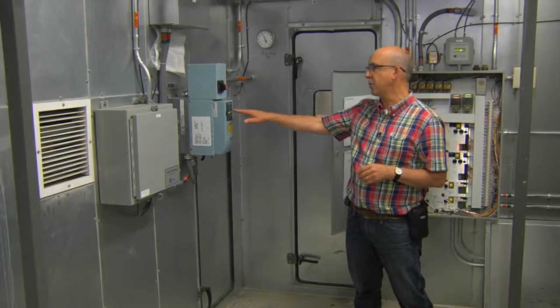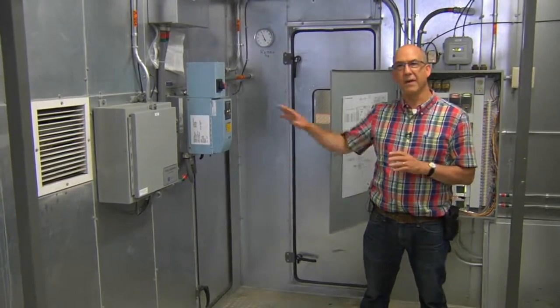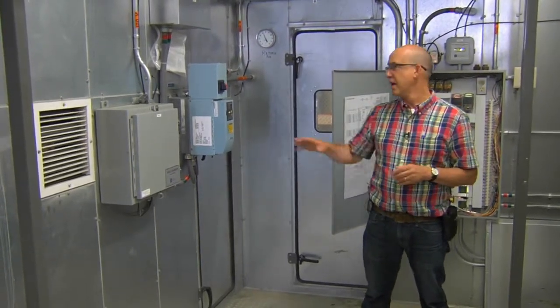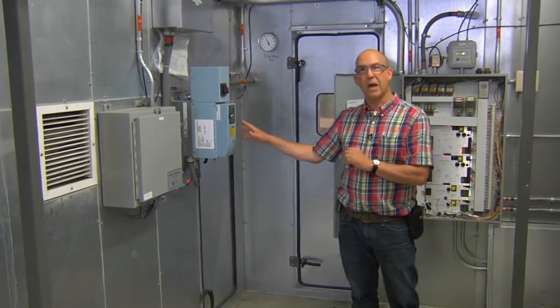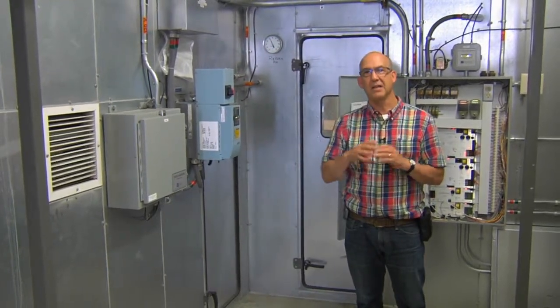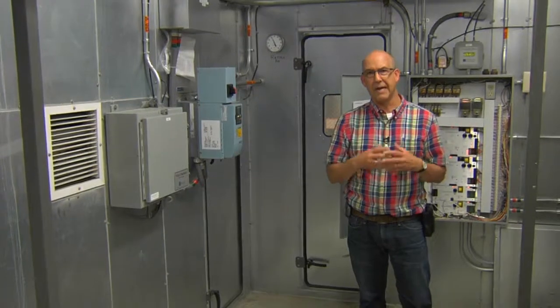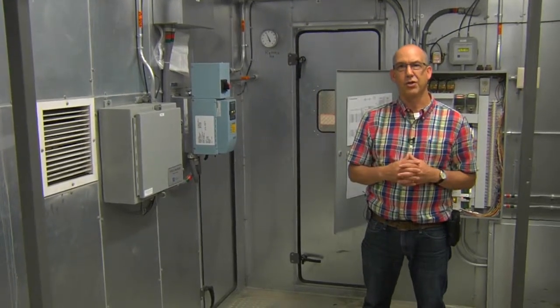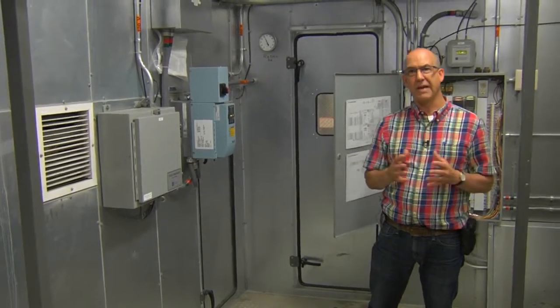We want to see stable output signal on VFDs, indicates good control. So in this case, the return fan's operating really well. The supply fan's behind us. The control loop, the PID loop might need to be looked at. There might be a sensor issue. It could be a belt or fan issue.